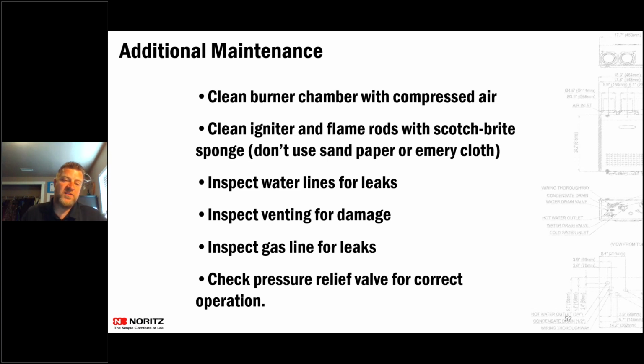But inspect water lines for leaks, inspect the venting for any damage, inspect that gas line, make sure that there's no leaks in that. And then always check that pressure relief valve to make sure that it's working properly. It works just like a T&P. You just pull it up, it'll shoot water out of it, you let it go, it'll shut off.